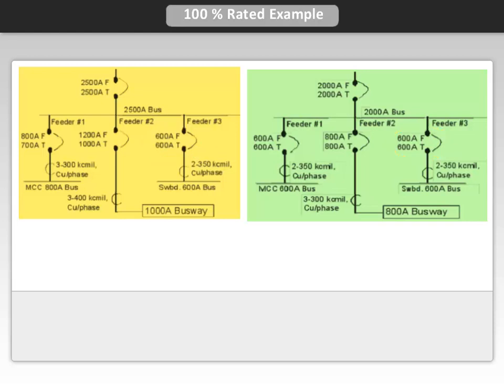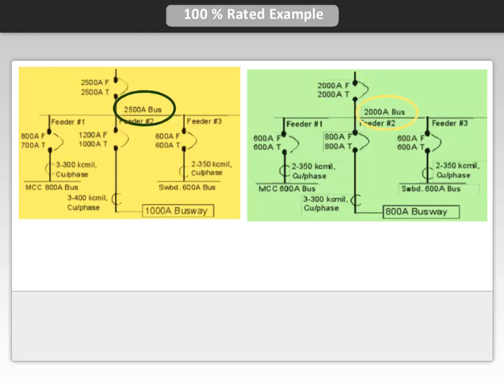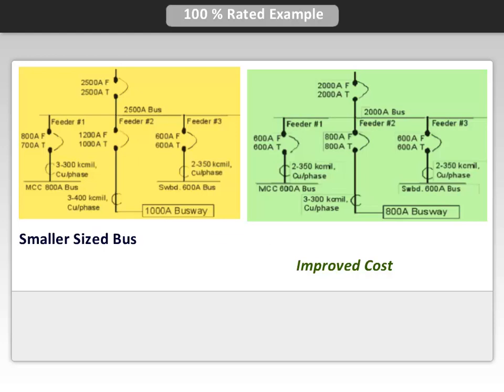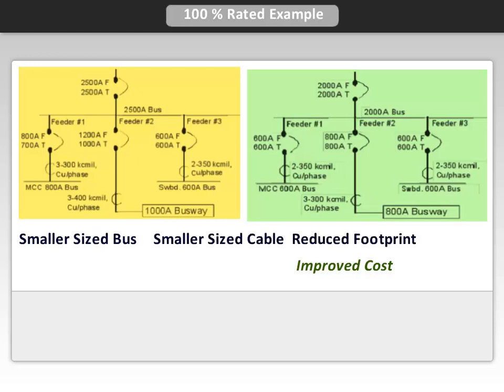Now remember, the total load was 2,000 amps. So the main breaker can be a 100% rated 2,000 amp breaker with a 2,000 amp trip, thus reducing the bus rating on the distribution switchboard to 2,000 amps. Using 100% rated breakers in this application allows for improved costs by using smaller bus and cable size, plus it reduces the footprint because of the smaller breaker sizes.